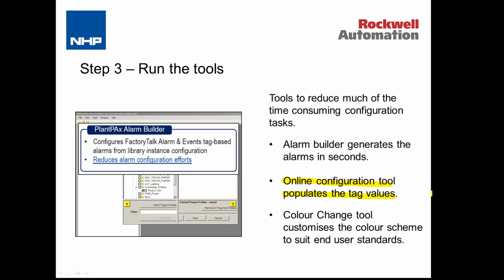A lot of that information will already be held in spreadsheets these days. We use spreadsheets a lot in engineering on our projects, so chances are we've already got a spreadsheet with all of our valve tag names and descriptions and alarms, and we can just take that information and use this online configuration tool to push all that information down to the controller. Another use for that tool is at the end of commissioning, to do an upload of the configuration into the spreadsheet, and that gives us a record of how the plant has been left at commissioning, which we can then use at a later date to compare to the current plant if there are any issues.